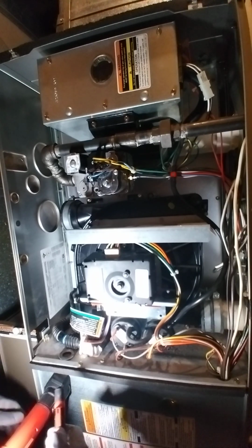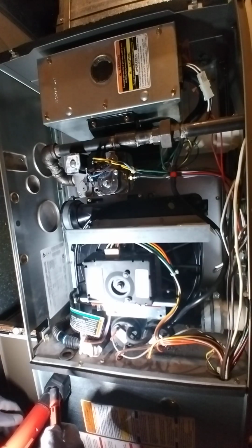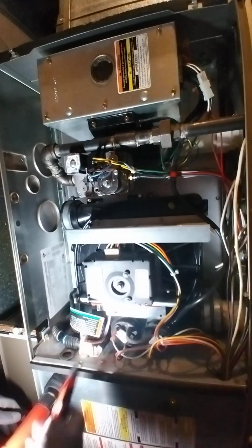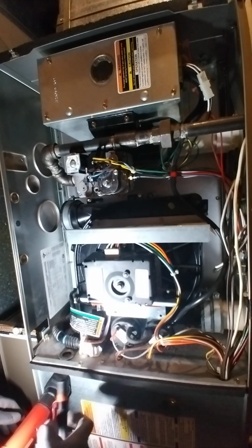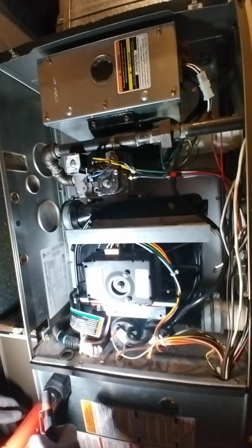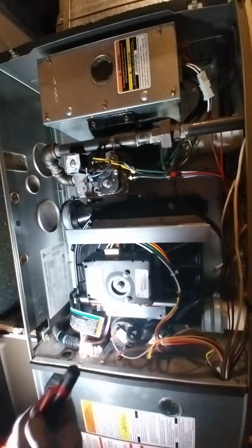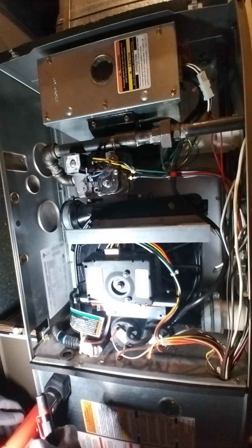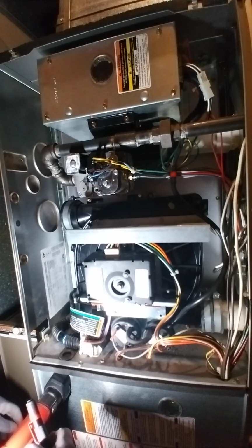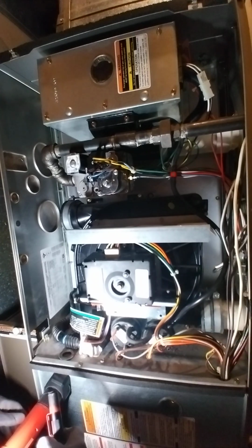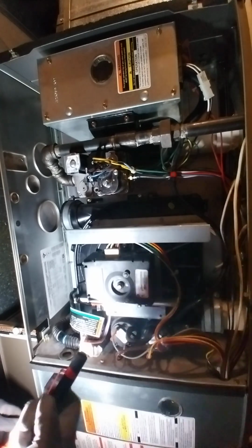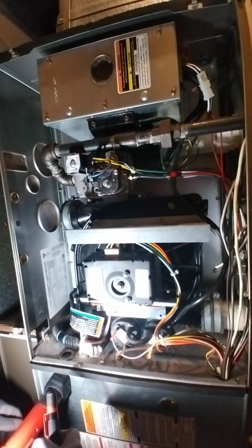The most common seems to be the return being clogged in some way that causes a rise in temperature to trip out the high temp sensor. Another thing I should mention that I checked was the flame sensor, the flame proving sensor. The furnace ran fine on low, so obviously it wasn't that sensor. But hopefully this helps somebody out there, because it seems to be kind of an oddball one. Maybe modern furnaces don't have this particular problem. I assume they all still have condensate traps, but maybe they're a little bit less susceptible to this particular issue.